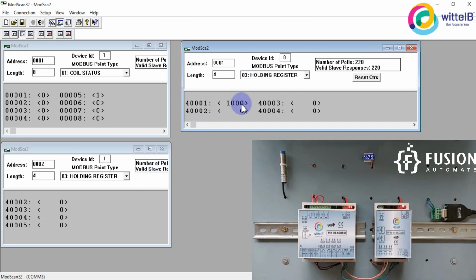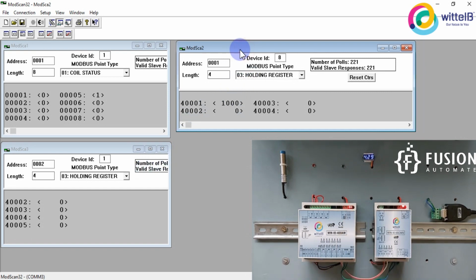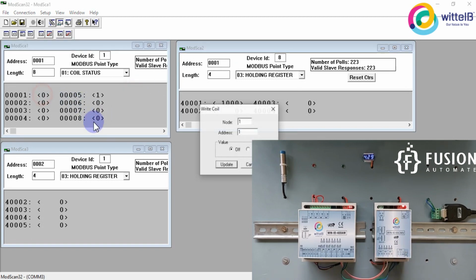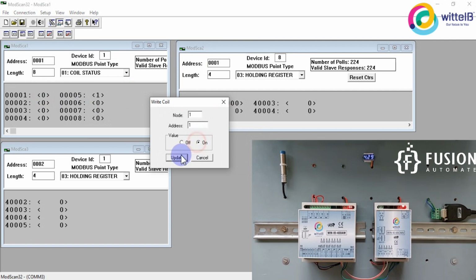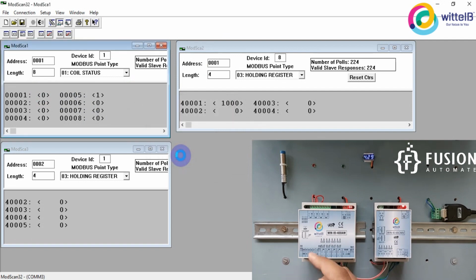So this is how you can test the analog output channel of this Modbus IO card, and this is how you can turn on and off your equipment in the field using Modscan software, and you can test your Modbus IO card. So if I place something here, then on coil status 5 you will see the value 0, because right now I have placed something on my sensor, and my sensor is not providing any voltage to this card, so that is why it is showing status as false.